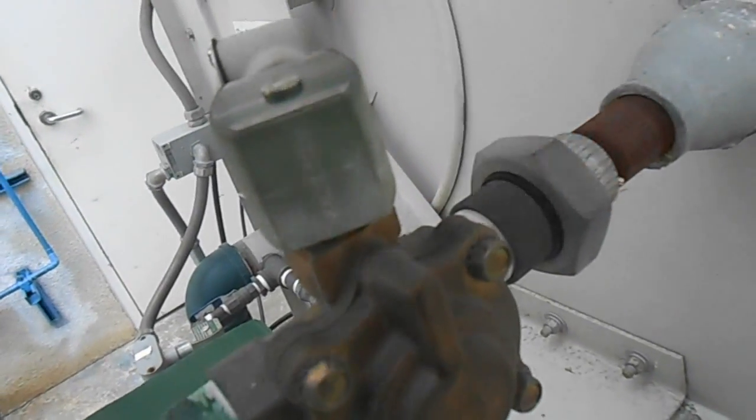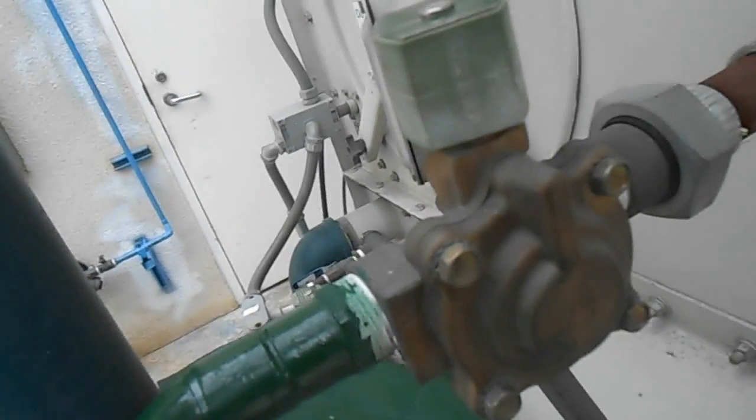Take apart this union over here, a little dielectric one, and replace that bad boy. Now this is a normally closed valve. I'll show you the wiring in a minute. It's normally closed, and then when it's energized, when the tower calls for makeup water, it opens.